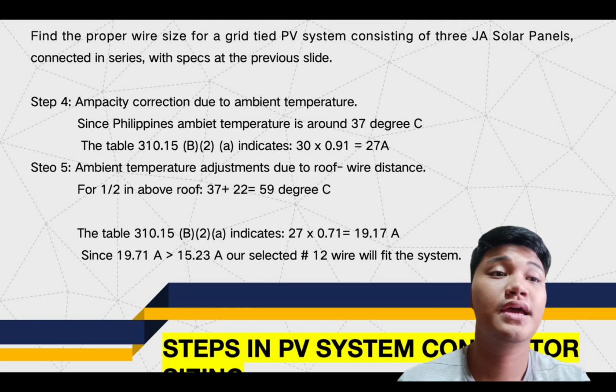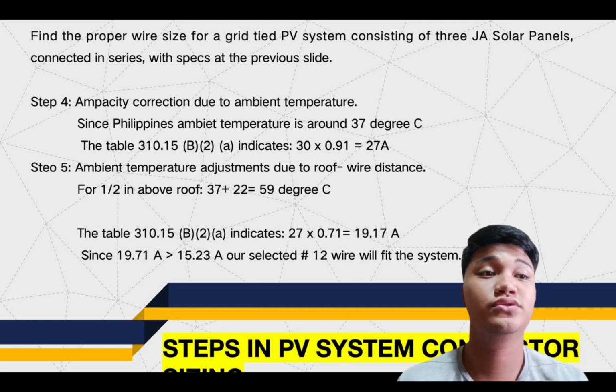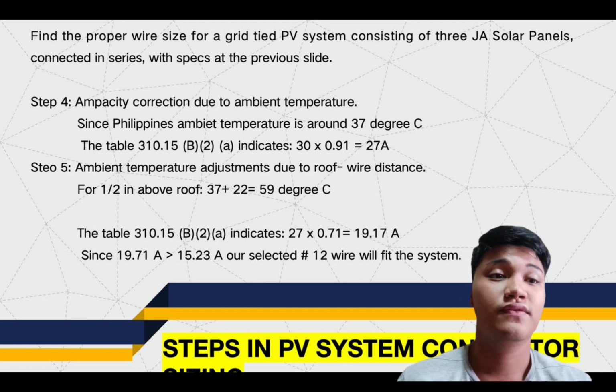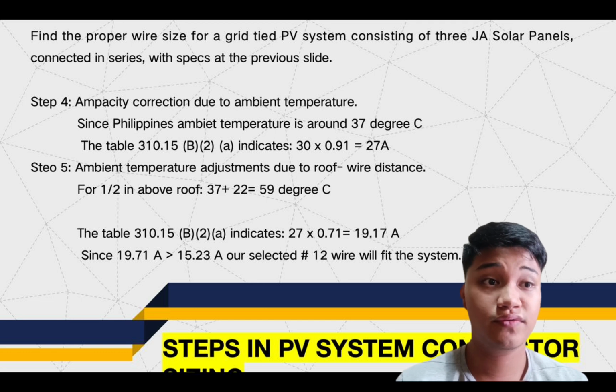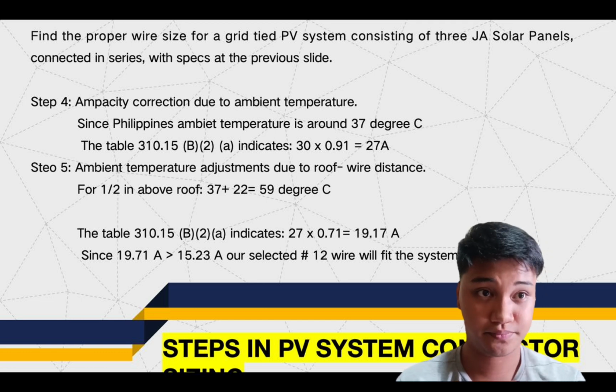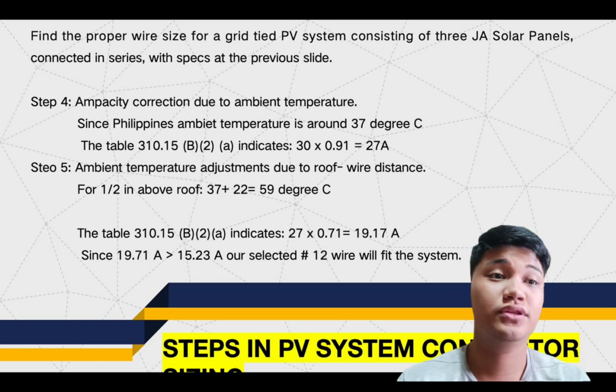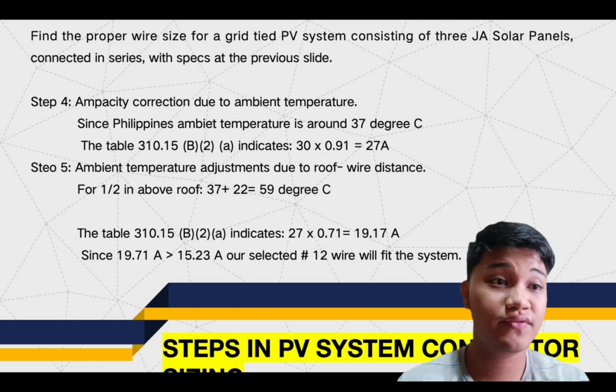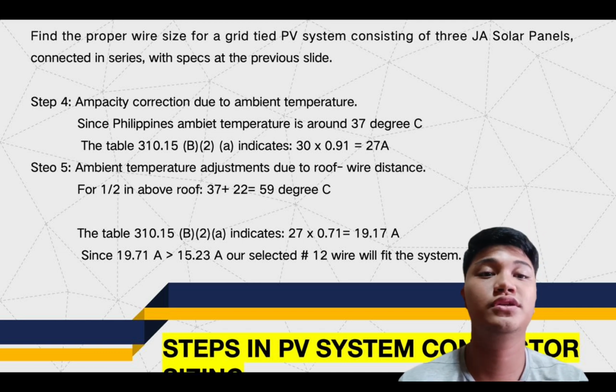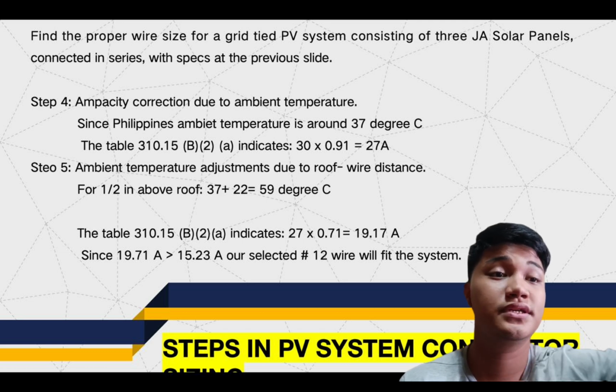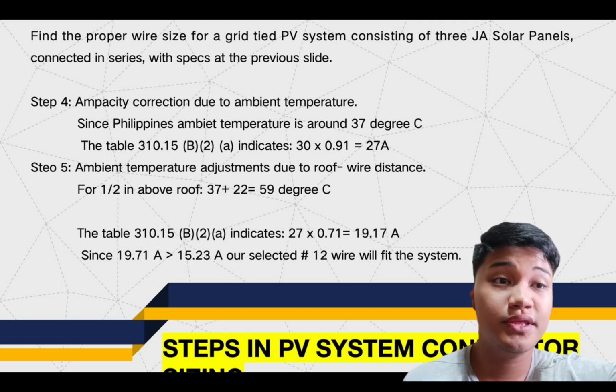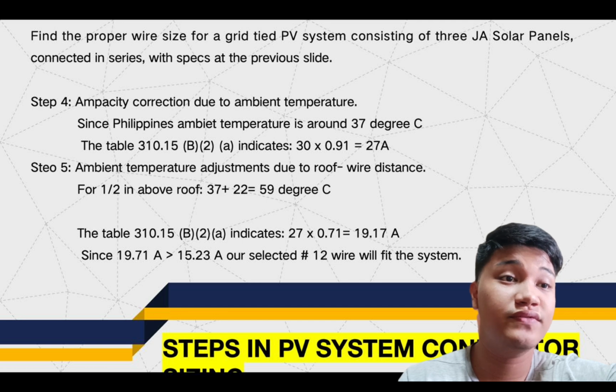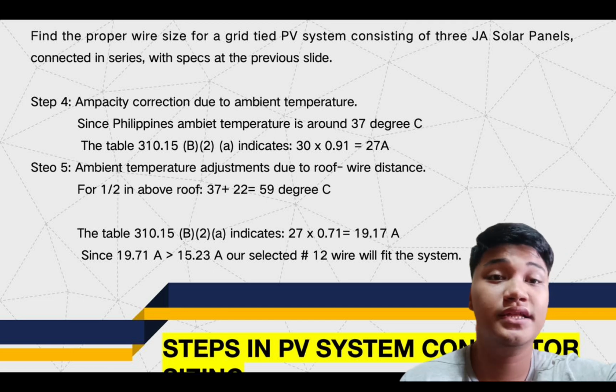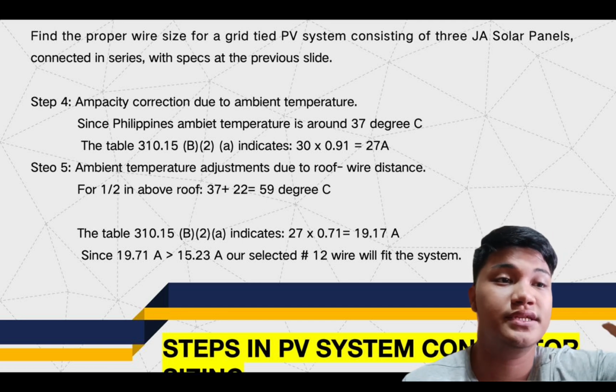Step 5 naman, ambient temperature adjustment due to roof wire distance. For 1/2 inch above the roof, 37 plus 22 is equals to 59 degrees Celsius. The table 310.15 indicates 27 times 0.71 is equals to 19.17 amperes. Since 19.17 amperes is greater than 15.23 amperes, our selected number 12 wire will fit the system.